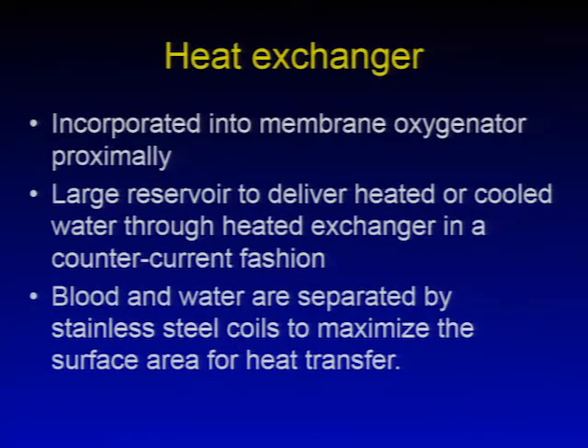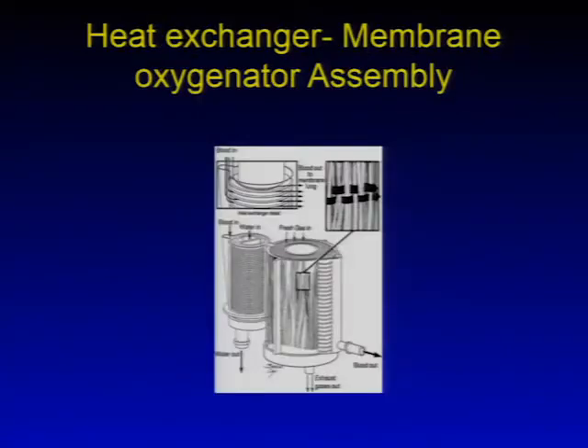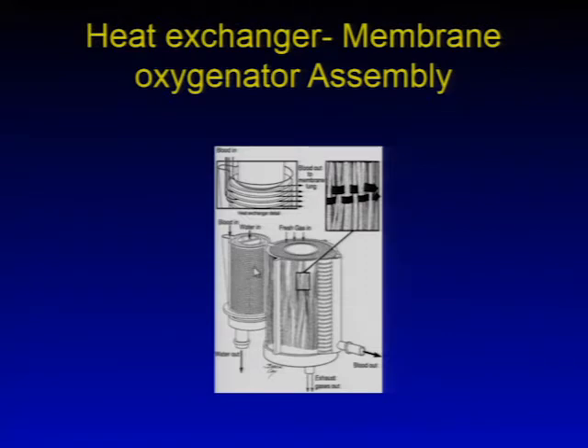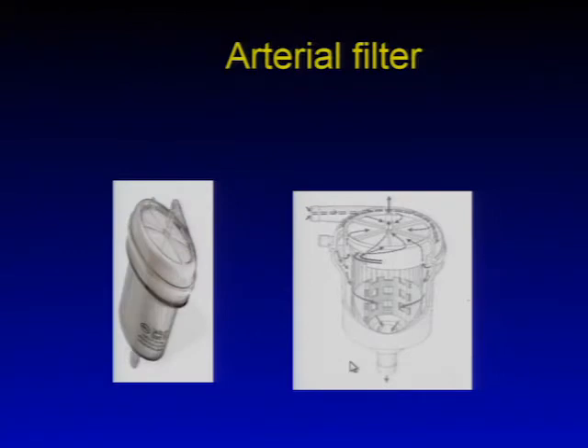Heat exchangers are incorporated into the membrane oxygenator proximally. There is a large reservoir to deliver heated or cold water through the heat exchanger in a counter-current fashion, with blood and water separated by stainless steel coils to maximize surface area for heat transfer. Blood enters the heat exchanger, is cooled or warmed depending on temperature, then enters the membrane oxygenator, gets oxygenated, and exits into the arterial line.